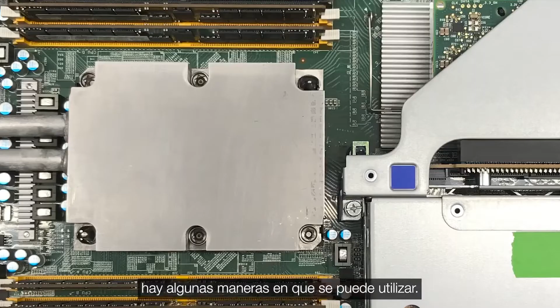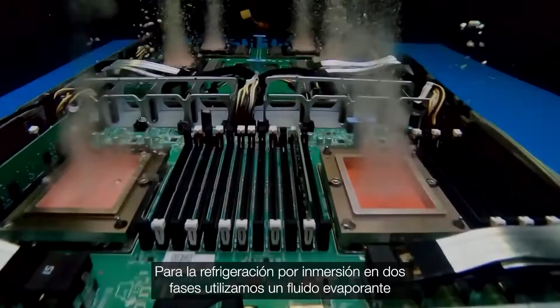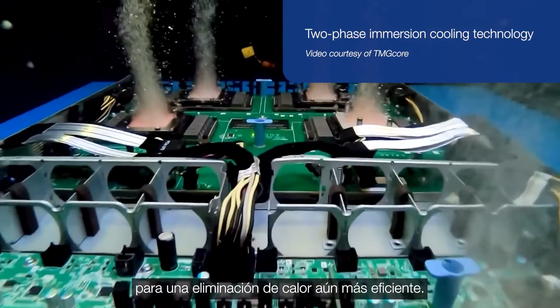When it comes to liquid cooling inside data centers, there are a few ways it can be utilized. First, we have direct-to-chip, where the hot components are cooled down by cold plates. Then we have one-phase immersion cooling, where the server is completely immersed in a bath of dielectric fluids that absorbs the heat of the electronics. For two-phase immersion cooling, we use an evaporating fluid for an even more efficient heat removal.